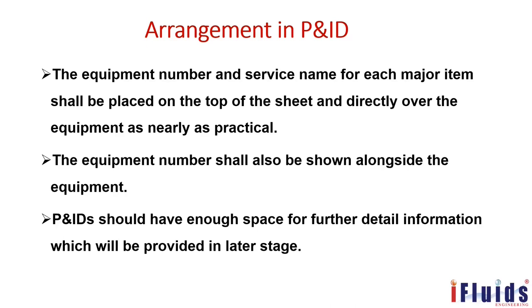The P&ID should have enough space for further detailed information to be provided at a later stage. If some vendor information is not yet available — for example, pump details not yet provided by the vendor — you should leave blank space. You should not place other equipment nearby that would make later-stage editing difficult. Leave space so that at the appropriate stage you can add the missing information.